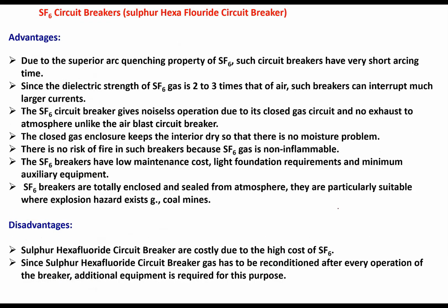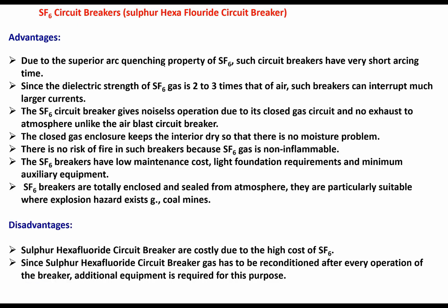So advantages of SF6. SF6 gas has the superior arc quenching property because of its electronegativity property. And the dielectric strength of SF6 gas is 2 to 3 times that of normal atmospheric air, because of which these breakers can interrupt very large currents, up to 60 kiloamperes.